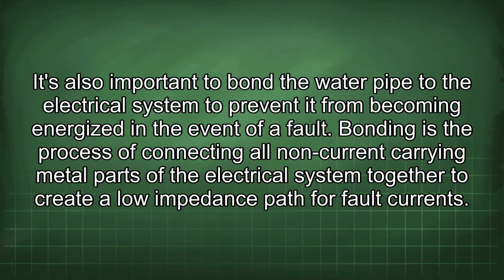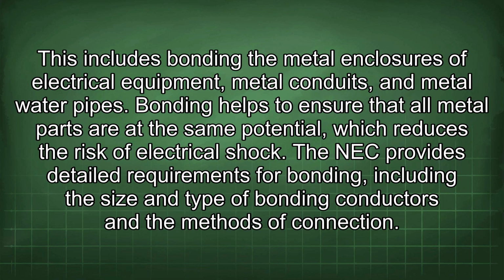It's also important to bond the water pipe to the electrical system to prevent it from becoming energized in the event of a fault. Bonding is the process of connecting all non-current carrying metal parts of the electrical system together to create a low impedance path for fault currents. This includes bonding the metal enclosures of electrical equipment, metal conduits, and metal water pipes. Bonding helps to ensure that all metal parts are at the same potential, which reduces the risk of electrical shock.